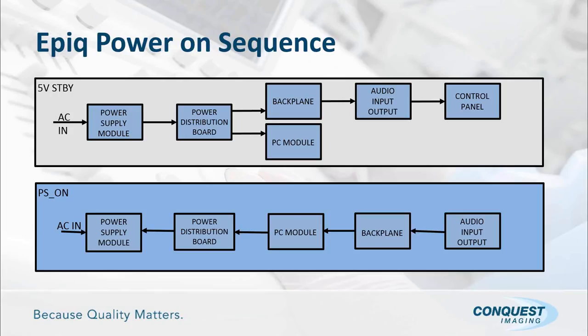So in the top one, we're talking about when we have 5 volt standby. Well, that's when we just simply plug the system into the wall. It's interesting to know that this is one of the few systems that do not have a circuit breaker on your platform power module. So you simply plug it in and there is power to the system. So we see that on the left-hand side of the top box, AC in. At that point, the power module generates 5 volt standby that gets shipped to the power distribution board and split up. One goes to the PC module and one goes through the backplane, through your audio input-output module, which I described earlier, and into your control panel where it's illustrated as a white button on your control panel.